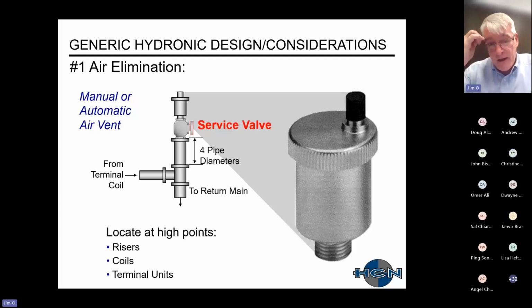I see them not installed as much as they should be, mostly on coils and terminal units. I would recommend putting them on a coil just because usually they have larger pipe sizes and a larger volume of water. With terminal units, do appreciate that this could get expensive at each of them, but maybe you would put one on strategic ones, et cetera.